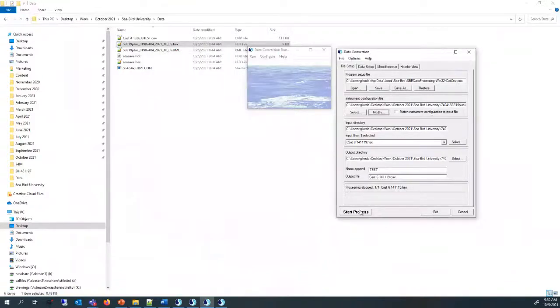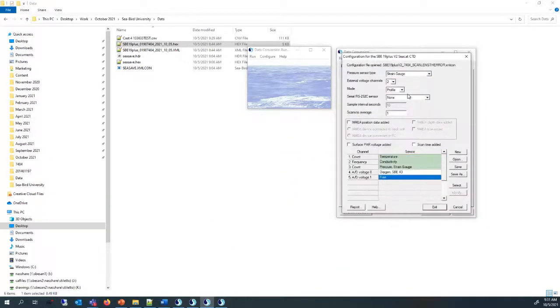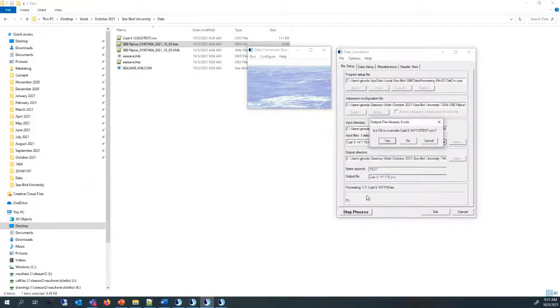So when I click start process, it's going to say processing stopped, and it's not really going to tell us why. So that's where you need to do some troubleshooting. It's almost always the fact that your hex file does not match your XML con file, at which point you should go in, try to identify in CTerm the configuration of your CTD, and then make sure that your XML con configuration file actually matches that config, and then you'll be able to process your data.